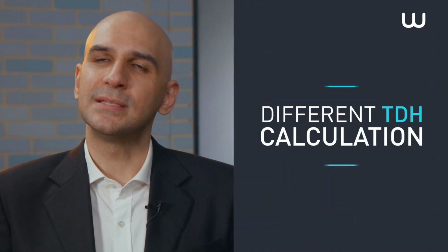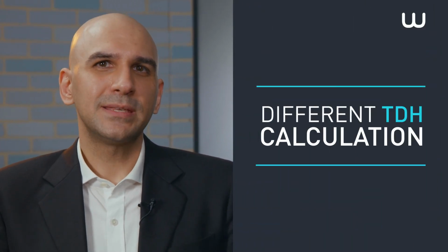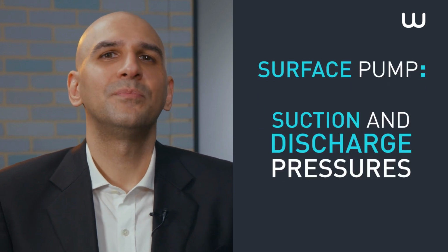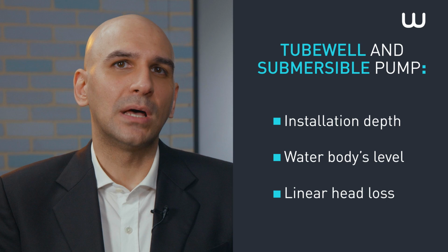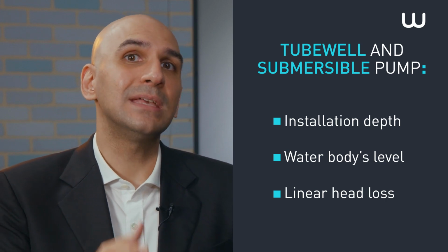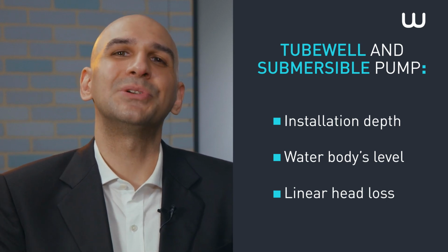What you need to remember. Depending on the type of site, the TDH calculation is not the same. In the case of a surface pump, the suction and discharge pressures are enough. In the case of an immersed pump in a tube well or a submersible wastewater pump, the TDH calculation takes into account the depth at which the pump was installed, the water body's level, and the linear head loss between the pump and the inlet where the discharge pressure is measured.